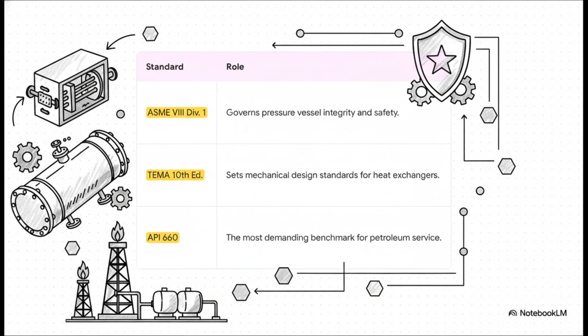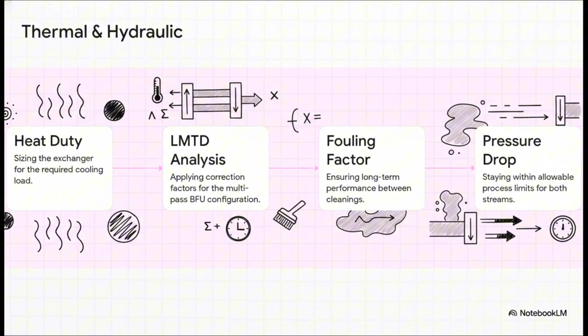Step one was all about performance, thermal and hydraulic. After calculating the exact heat load, the team did a detailed LMTD analysis. This is critical because with the multi-pass U-tube design, the simple formula doesn't work, you need correction factors to get an accurate temperature profile. They also engineered in fouling factors, planning for the inevitable buildup inside the tubes, ensuring the cooler performs perfectly right up until its next scheduled cleaning.